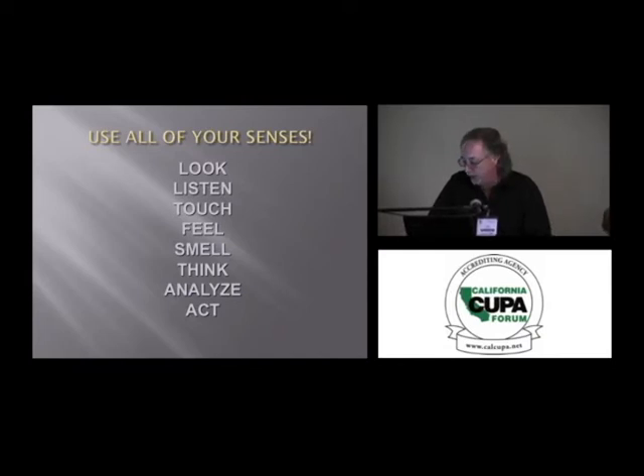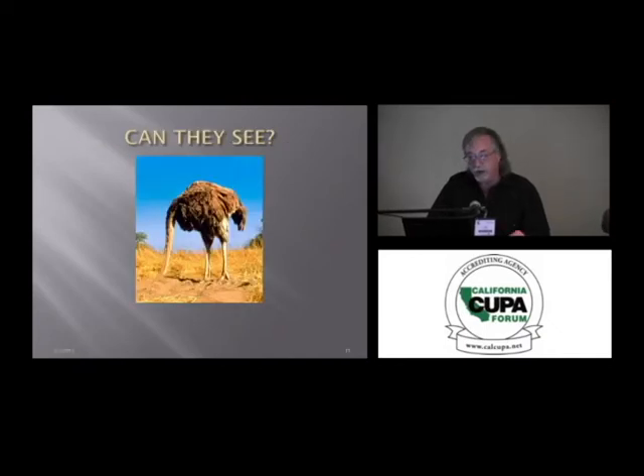Think about what you're looking at, get together with the site, and come up with a plan. It seems like they walk through the plants every day, they do daily rounds, but they keep their heads in the sand. So all too often we have operators that write numbers down on daily round sheets, but they don't use them, they don't apply them, they don't even know what they mean. So training is a big part of mechanical integrity. If they don't know what they're looking at, they're not going to be able to keep their systems mechanically sound. They should have documentation of the minimal requirements, which is SOPs, overview of the system, basic refrigeration, etc.